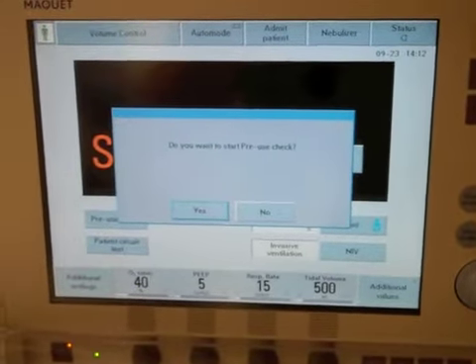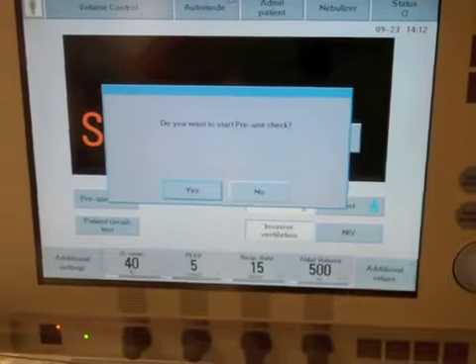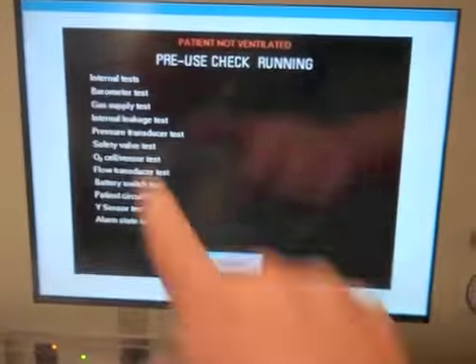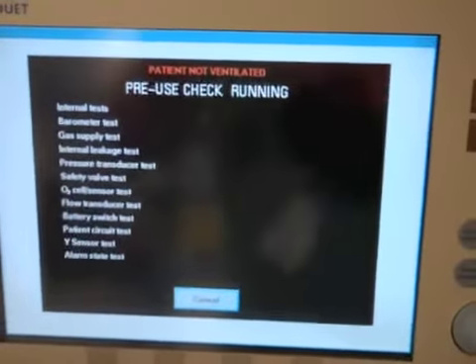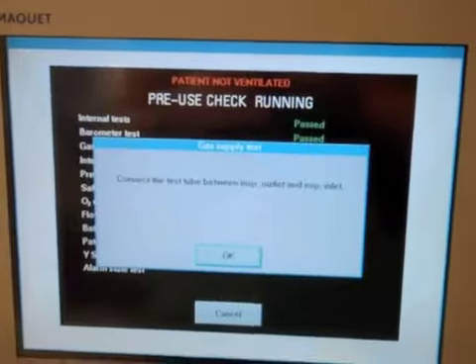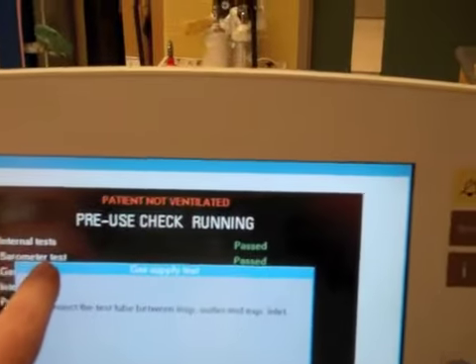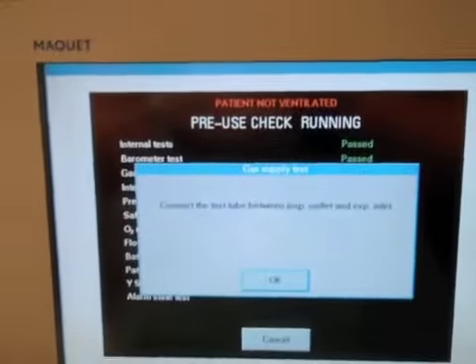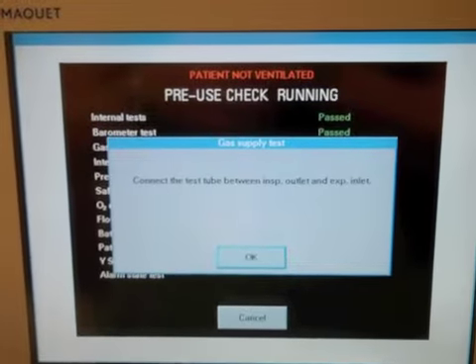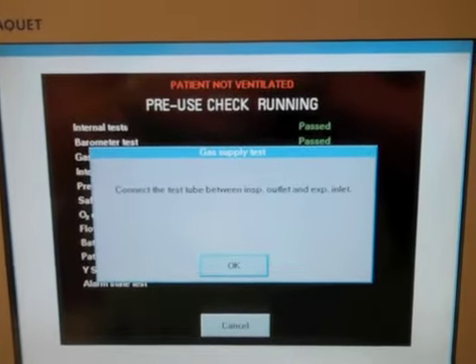So it's asking, do you want to do a pre-start check? And we're going to go ahead and say yes. And it's going to get right into it. So first thing it's doing is an internal test. So it's running this test already. It's past that. First it's done a barometer test, so it's checked barometric pressure. It's now saying to connect the test tube between inspiratory and expiratory side.